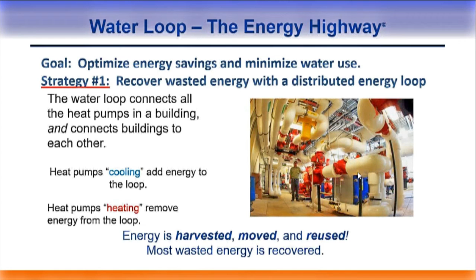So we started building. The backbone is an 18-inch pipeline. The main mechanical room for this initial program is 20 by 40 feet, with a little bit of work overhead. In there I housed my main system pumps and the heat exchangers to the cooling tower I got out of this deal, the 500-ton tower, a boiler that existed, a chiller that existed. We used the chiller directly on the loop too, plus all of the metering, monitoring, corrosion protection, and the fire riser down at the other end. So the first thing they liked was the amount of space it took, or didn't take.